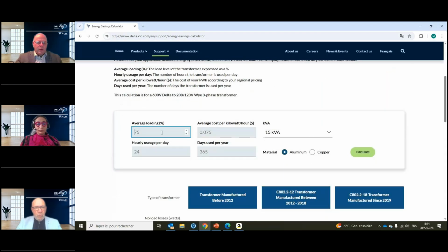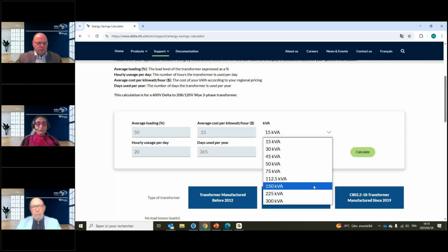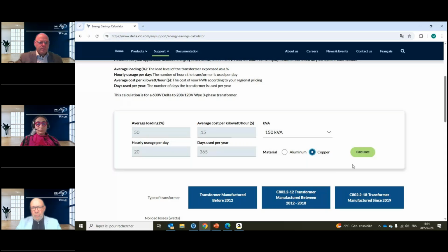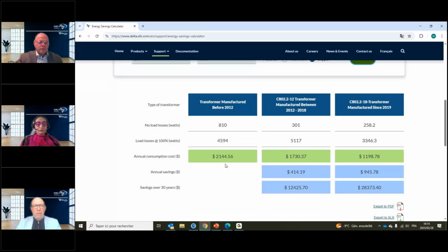So let's say our transformer is loaded at 50%. My cost of energy is 15 cents a kilowatt hour. I'm using my transformer 24 hours a day, or let's say we're having a break, it's only 20 hours a day, and it's 365 days a year. I'm looking at a 150 kVA transformer made of copper. And then I just push calculate, and all those fields will populate.